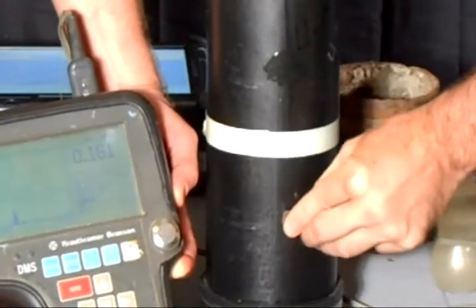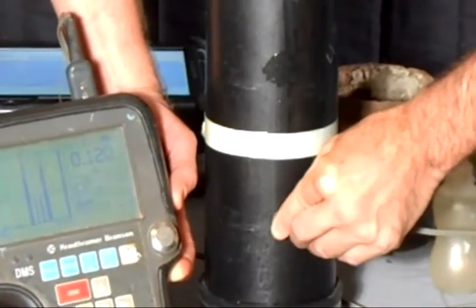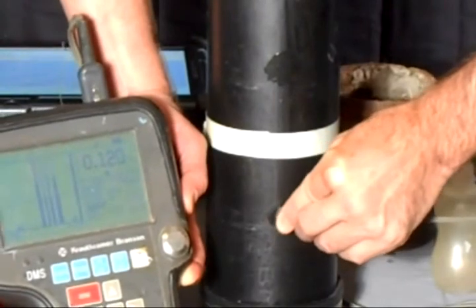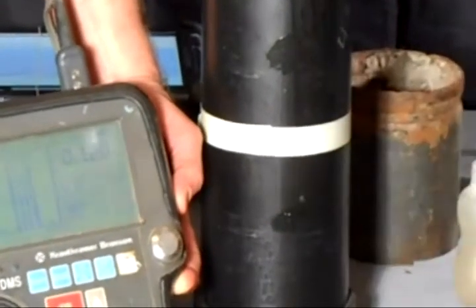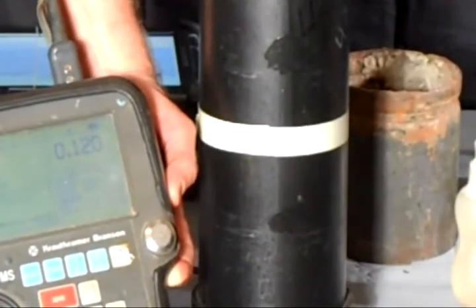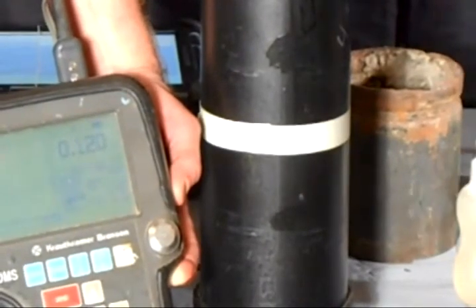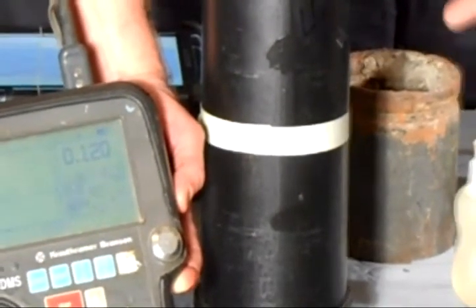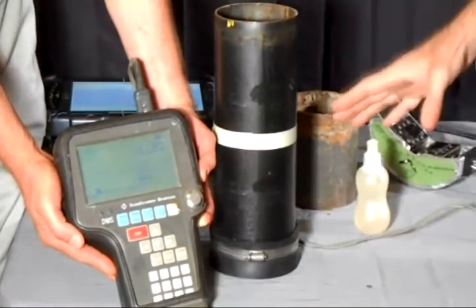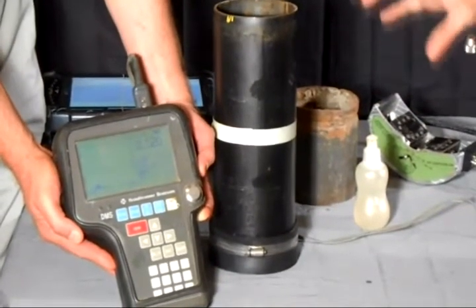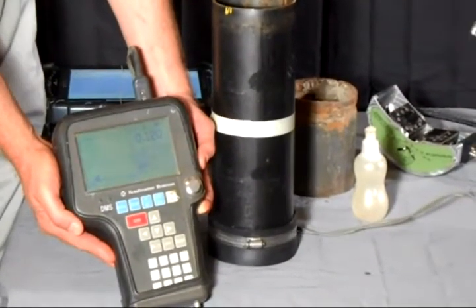Now I'm going to move the probe down to the lower half of the pipe where the water is, and you're going to see it's the same measurement, 120 thousandths. Important thing to note here is that the measurement is exactly the same between the wet and the dry side, which it should be because that's the wall thickness on the pipe, but you can't tell the difference between where there's water and where the pipe is dry.